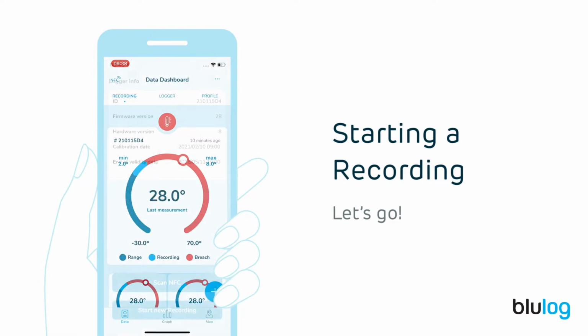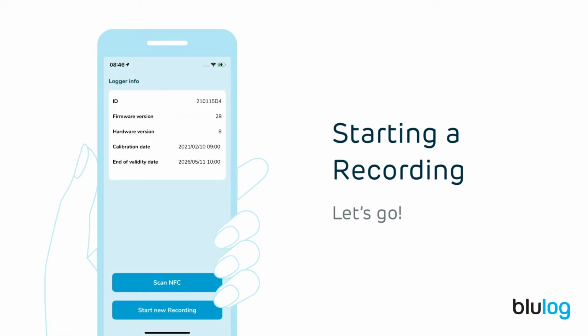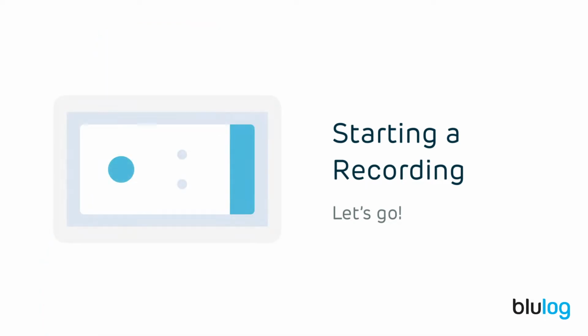If the recording has not started yet, it comes with more basic information, like here. Please wait a few more seconds and scan again. If you have chosen the manual start, press the push start button visible on the logger for around 3 seconds until you see both diodes blinking.